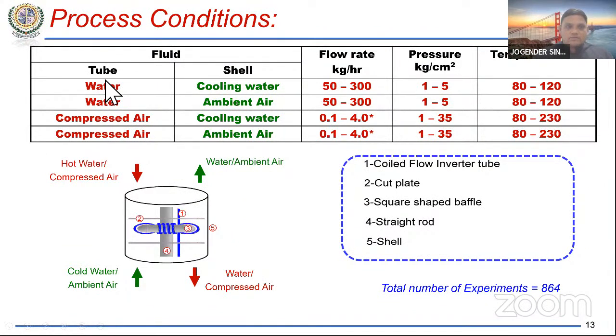Now, this is what I was talking about, the process conditions. We used water in the tube and cooling water in the shell side, then hot water in the tube and ambient air in the shell side. And these were the flow rates for these different types of flow arrangements. For water, we kept the flow rate at 50 to 300 kg per hour, which is pretty high, to test at higher flow rates so that we can meet some industrial standards. Then the pressure inside those tubes was 1 to 5 kg per centimeter square. Temperature we varied, in the case of water on the tube side, from 80 to 120 degrees Celsius. In the case of compressed air on the tube side, we varied the temperature from 80 to 230 degrees Celsius.